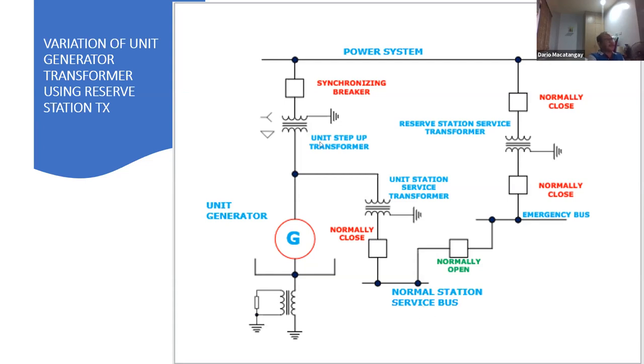So when you're doing maintenance on this generator, then this will be open, this will be open, this will be open, this breaker here will be open. You can see my cursor here, Patty, can you see it? So the cursor, Patty, hello? Yes sir, I can see it. You can see the cursor, right? Yes, the cursor. Okay, so this breaker here will be open, and this one will be closed. So they can actually maintain this whole thing with this reserve station service transformer energized.